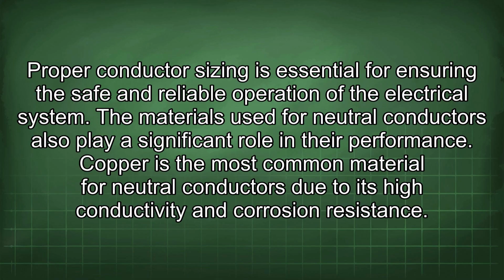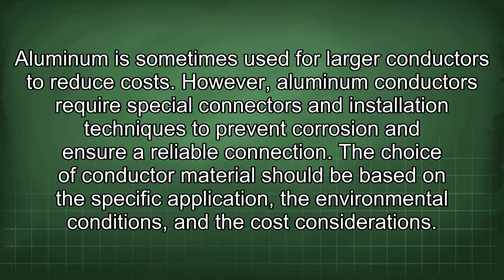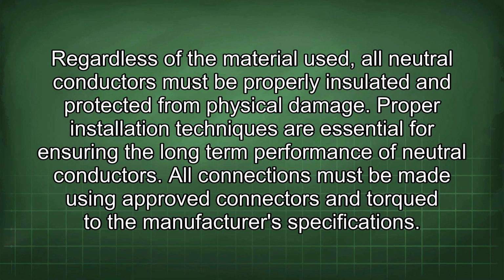The materials used for neutral conductors also play a significant role in their performance. Copper is the most common material for neutral conductors due to its high conductivity and corrosion resistance. Aluminum is sometimes used for larger conductors to reduce costs. However, aluminum conductors require special connectors and installation techniques to prevent corrosion and ensure a reliable connection. The choice of conductor material should be based on the specific application, the environmental conditions, and the cost considerations. Regardless of the material used, all neutral conductors must be properly insulated and protected from physical damage.